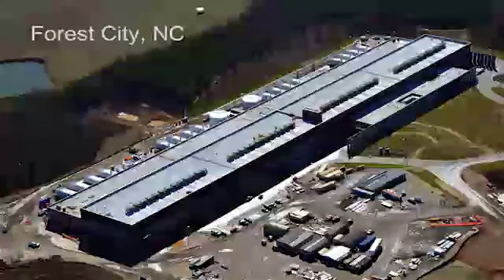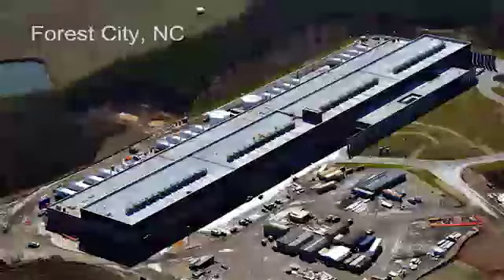We found we could still operate at 100% outside air in evaporative mode because relative humidity would peak in the early morning when it was cooler, then drop as the day warmed up, keeping us within our psychrometric envelope. Our bin data said we didn't need other mechanical cooling, but the ASHRAE 50-year data indicated about 50 hours a year where some trimming might be needed.